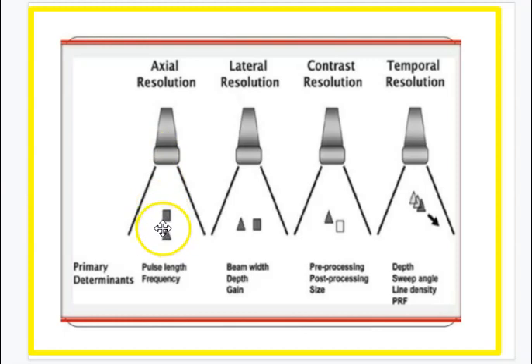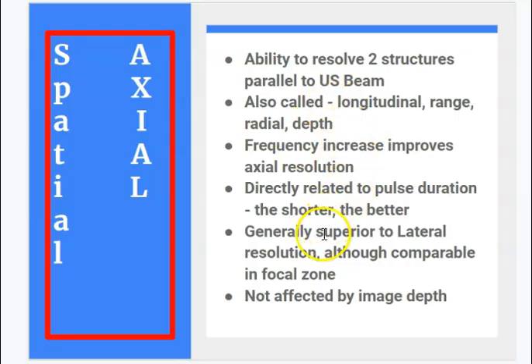Just think about that. We have to be able to see between these two objects. A shorter pulse allows the pulse to come down, go back, come down, and go back, and better define these objects that are actually separate from each other. If this was a longer pulse, it would go down and perhaps not fit between these two objects, and therefore wouldn't be able to differentiate them as two different objects. Axial resolution is generally superior to lateral resolution, although comparable in the focal zone of the transducer, and it is not affected by image depth.